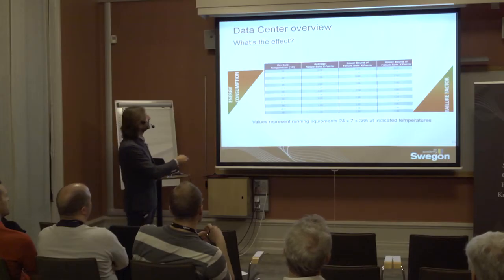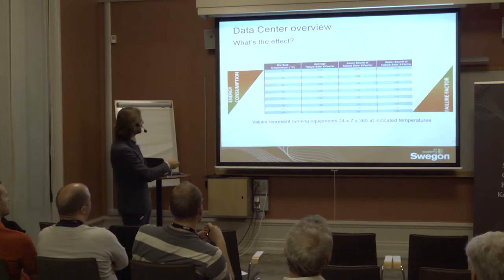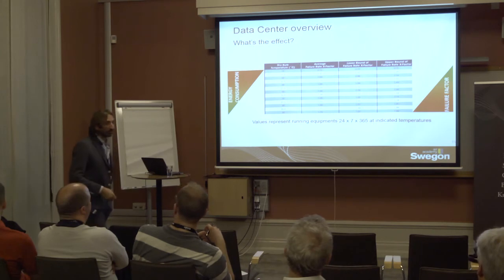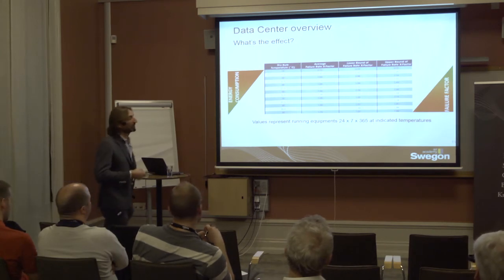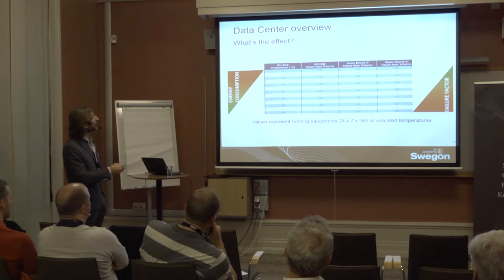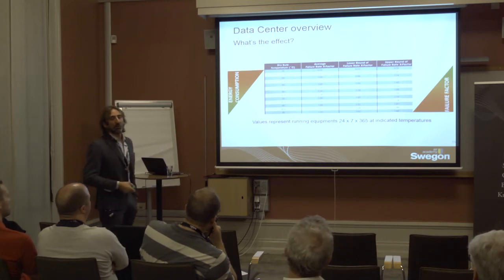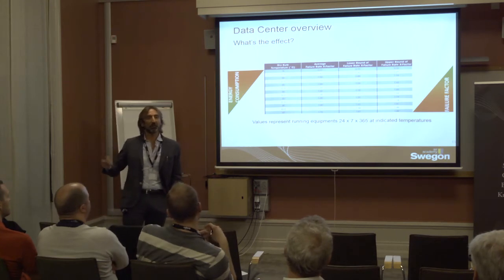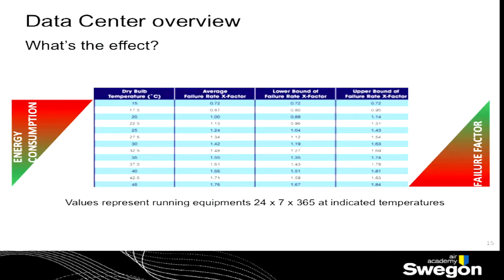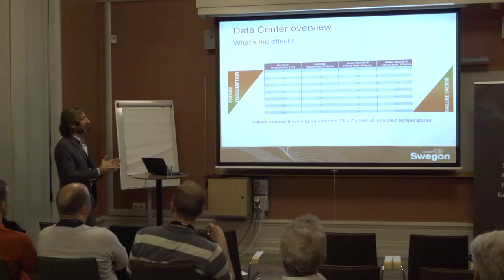But what does it mean? That this is the right average failure factor? No, this is the failure factor that is calculated with 24 hours a day, 7 days per week, and 365 days per year working in these conditions. So if you define, for example, a cooling system that is able to make your system stable at 25 degrees, let's say, or 22 degrees, 22.5 degrees for most of the year, but you don't want to take care about the temperature peaks that you can have during 3 or 4 or 10 days in a year, it means that you are not working in very bad conditions, because this factor will not increase so much if you don't work all the year long in this kind of condition. So you have to be very careful in evaluating these kind of numbers.